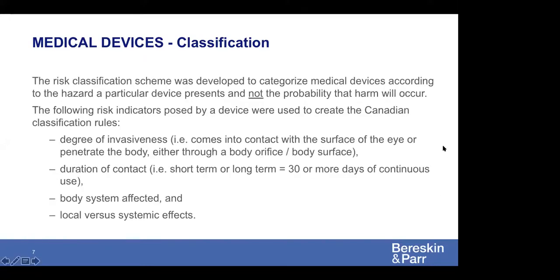The classification rules are based on a number of risk factors posed by the device. So for example, the rules ask, what's the degree of invasiveness of the device? Does it come into contact with the surface of the eye, or does it penetrate the body either through a body orifice or through the surface of the body? What's the duration of contact? Is it short-term or is it long-term? Long-term is defined as 30 or more days of continuous use. The rules ask, what is the body system that is affected? And then finally, are the effects on the body local, or are they systemic? Next slide, please.